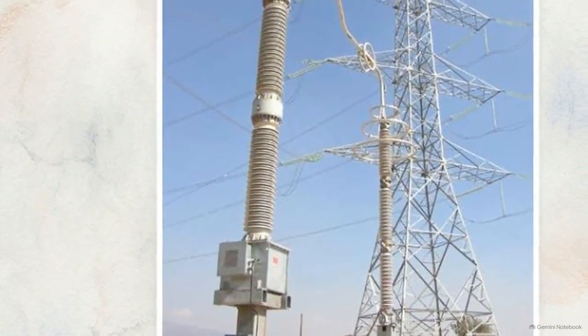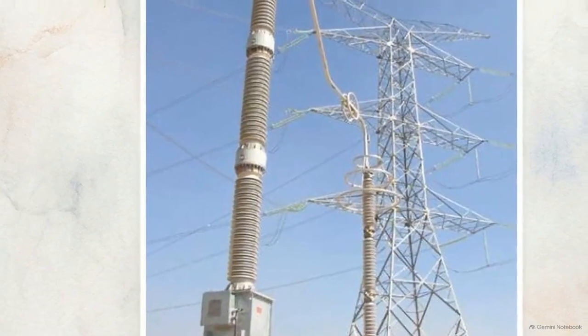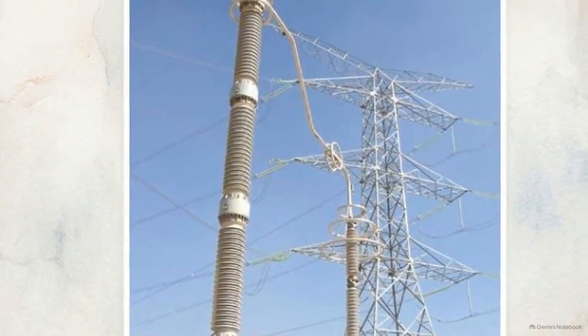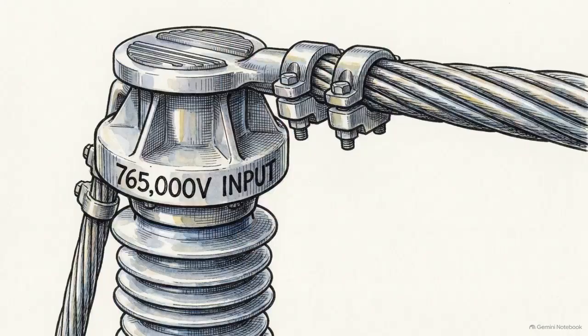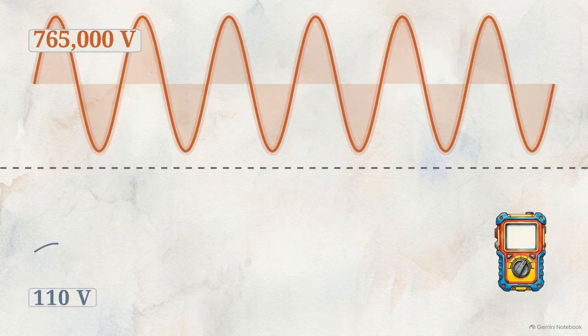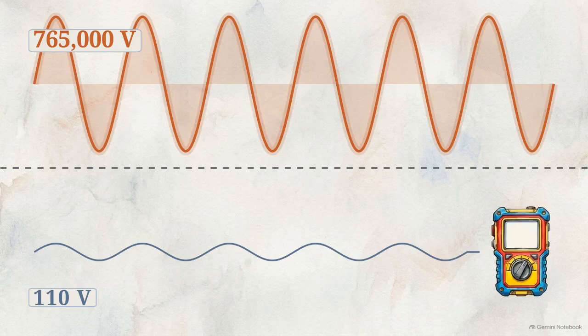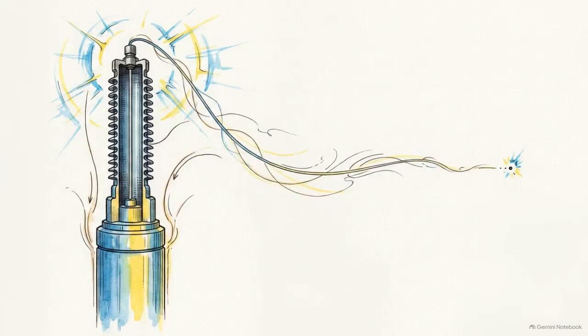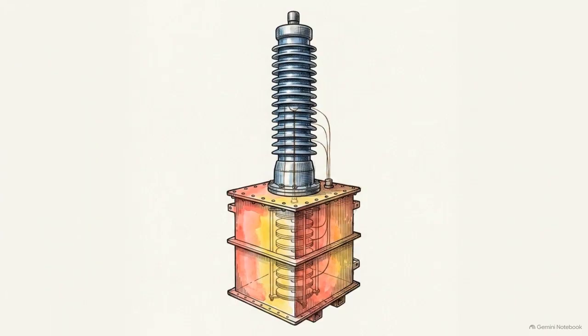This photograph shows the industry-standard hardware used to solve that exact problem, the Capacitor Voltage Transformer, or CVT. Its entire purpose is to take the 765,000 volts from the overhead transmission lines and safely step it down to a standard 110-volt output that sensitive metering equipment can read. Achieving a step-down ratio of nearly 7,000 to 1 without destroying the equipment requires abandoning pure magnetic induction. Instead, the CVT relies on a two-stage internal architecture.